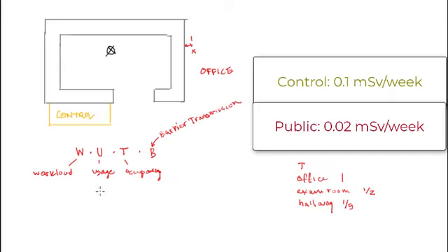So all these factors together, then, you divide by the distance squared, because there's a 1 over r squared falloff the farther you get away. And that total then is P. That's your goal. So after you have designed the right barrier, the P value should be less than or equal to what you want to achieve.